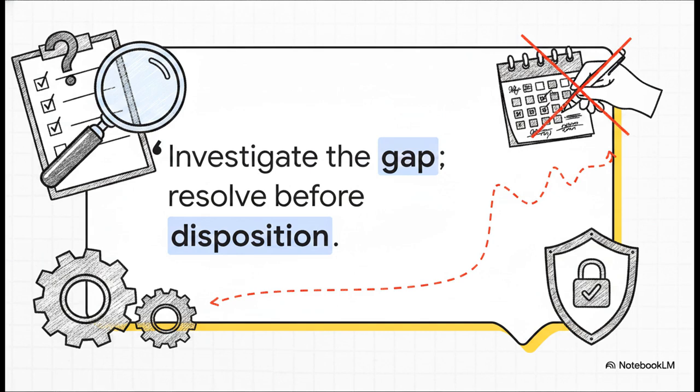Strong final test results do not magically cure an incomplete record. You must formally investigate that gap, and whatever you do, never let someone go back and sign it from memory days later. Without that original signature, there is zero proof the check actually happened, and back-signing is falsification. Investigate and resolve the gap first, always.